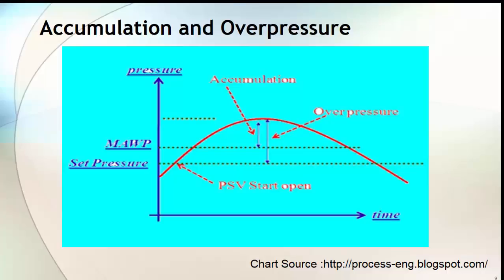The third line I will explain later on. Once the operating pressure starts increasing and reaches the PSV set pressure, the PSV starts opening. But at this stage, the PSV is not fully open. Hence pressure buildup will continue until the PSV is fully open. PSVs are designed in such a way that they will not allow the accumulation of pressure inside the vessel beyond the limit defined in the design code.